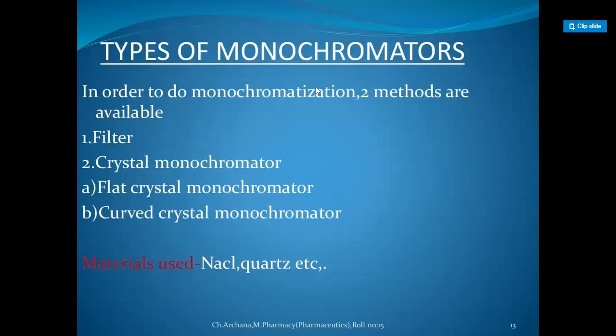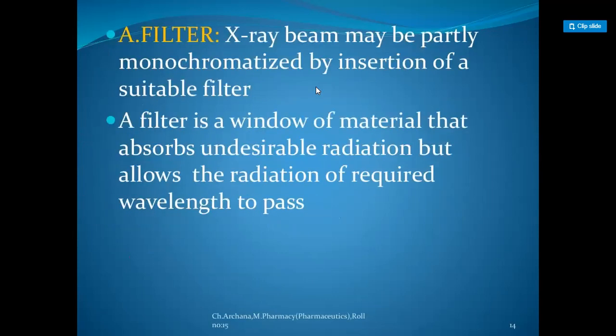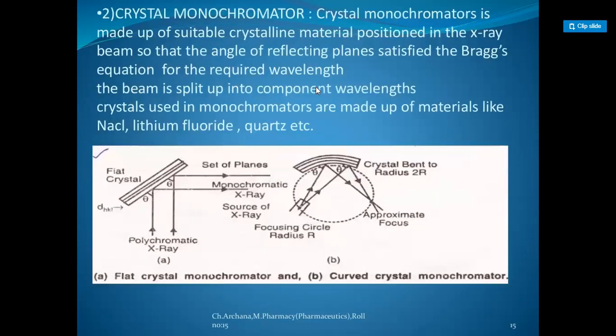For monochromatization, two methods are available: the filter method and crystal monochromators. The X-ray beam may be partly monochromatized by insertion of a suitable filter. A filter is a window of material that absorbs undesirable radiation but allows radiation of the required wavelength to pass.